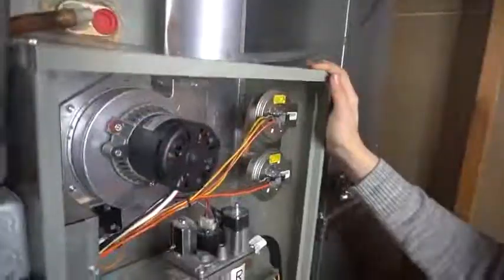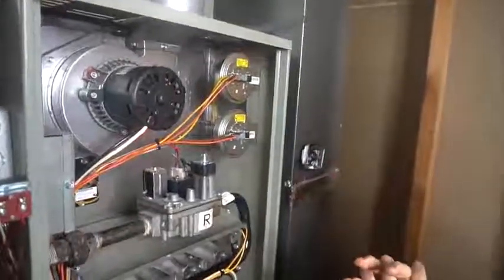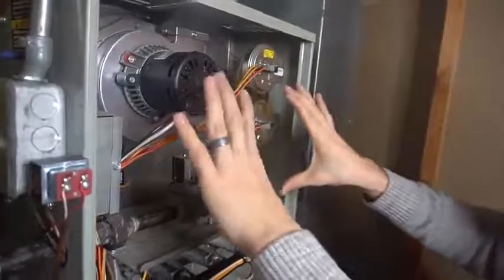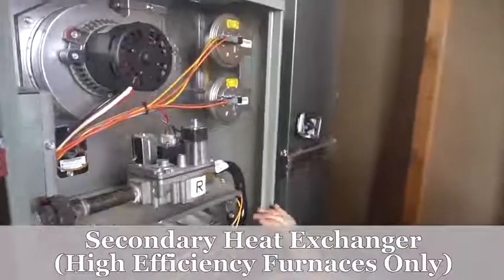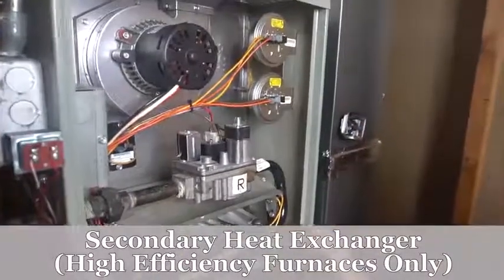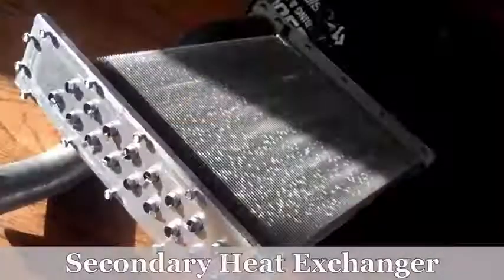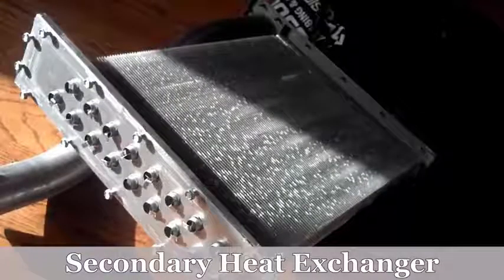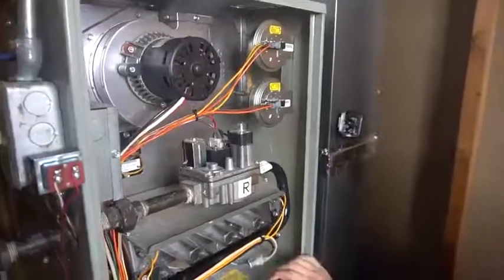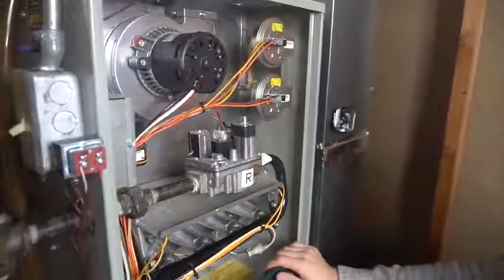That air going past that heat exchanger heats up and it goes out your supply duct, to warm up the rest of your house. And you should also know that high efficiency furnaces, they'll have a primary heat exchanger and a secondary heat exchanger. So they'll have two. And in the second one, there's actually condensation because when the combustion gases cool off enough, they start to condense and create water. So the secondary heat exchanger is actually built to be able to handle water and not rust out.